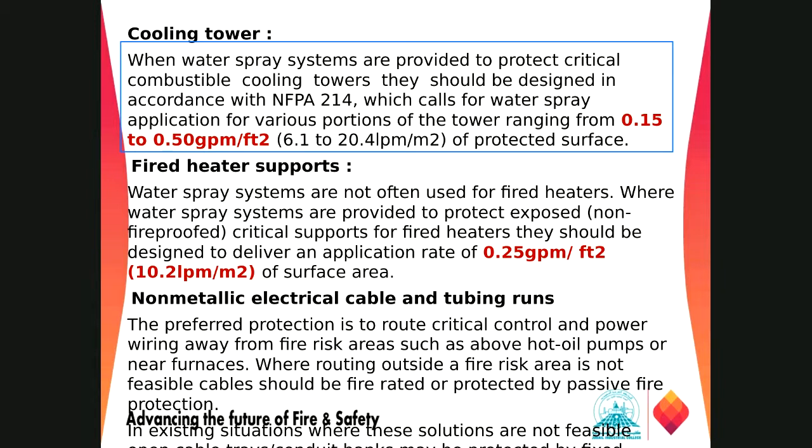Now my question is, why do we need protection in the cooling tower? We have plenty of water in the cooling towers, so what is the water spray system for in those areas? To protect the structure, because if the structure gets exposed to heat, it will lose its mechanical strength and will fall.